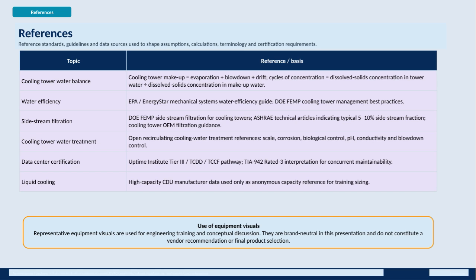Regarding water efficiency, we drew on authoritative sources, such as the EPA and Energy Star Mechanical Systems Water Efficiency Guide, along with the DOE's Federal Energy Management Program best practices for cooling tower management. For side stream filtration, we reference DOE guidelines, ASHRAE technical articles specifying typical filtration flow fractions, and original equipment manufacturer recommendations, all pointing to a side stream flow rate of around 5 to 10%.